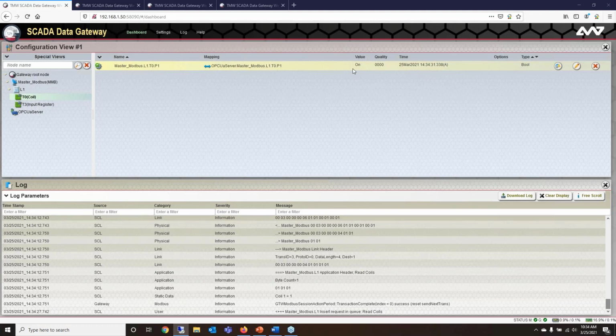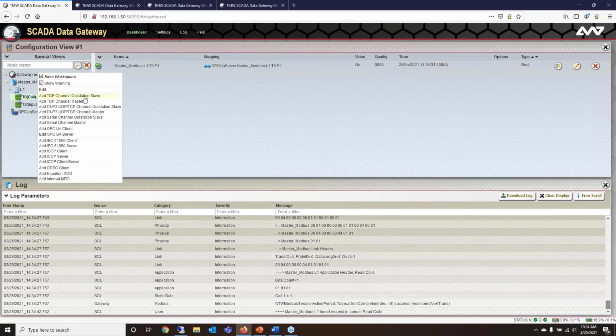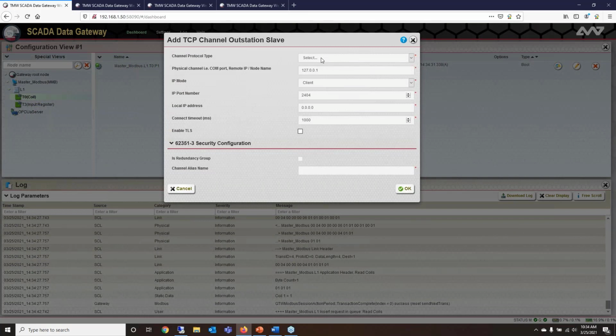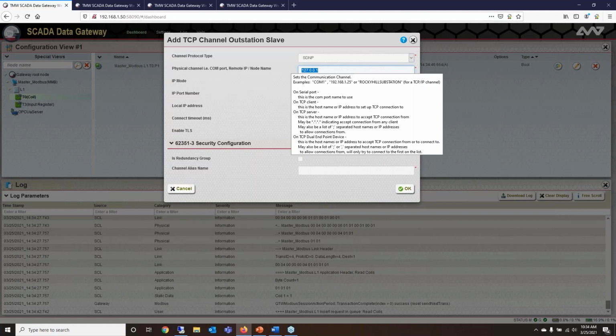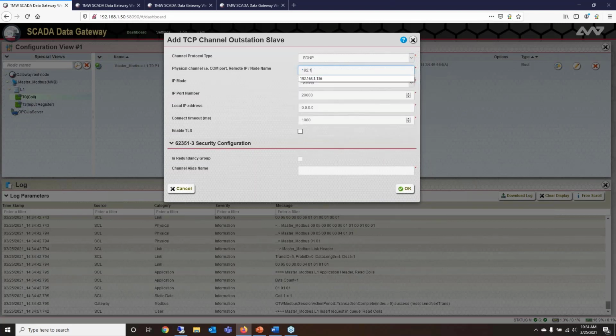How do we get this into the database that our control center, which is DNP3, is going to be able to monitor? Well, we're going to follow the same process. We're going to right-click here, and then we're going to add a TCP channel. We're going to choose this outstation. Again, it's going to look very similar. You're going to click this drop-down, and we're going to select a DNP3 outstation. Following the same logic, I'm going to tell it where its control station is going to be. And I'm going to give it its own IP address as well. And I'll name this outstation, DNP3 outstation.